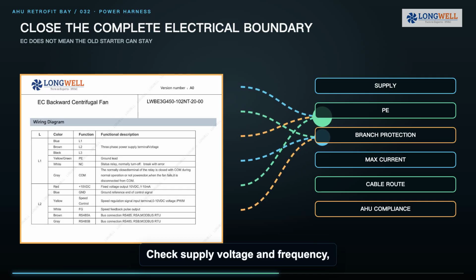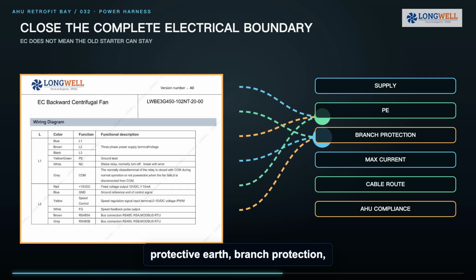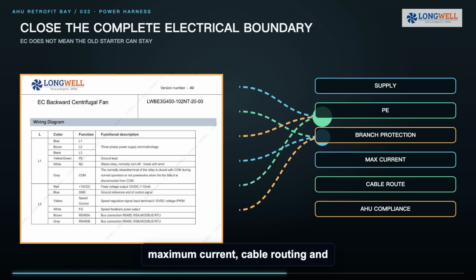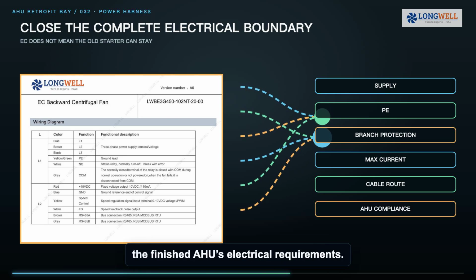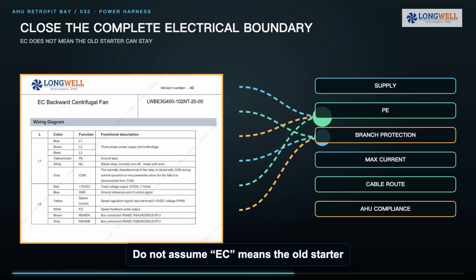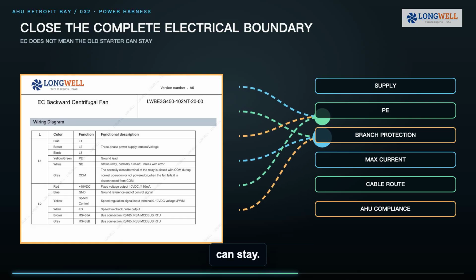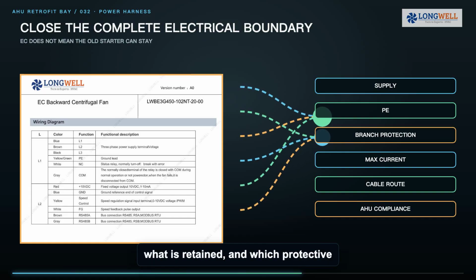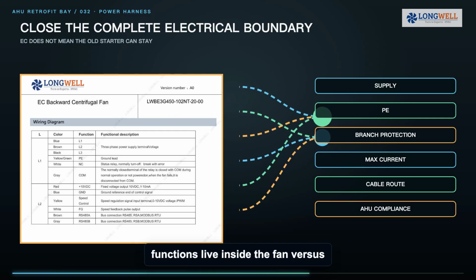Check supply voltage and frequency, protective earth, branch protection, maximum current, cable routing and the finished AHU's electrical requirements. Do not assume EC means the old starter can stay. Document what is removed, what is retained, and which protective functions live inside the fan versus the panel.